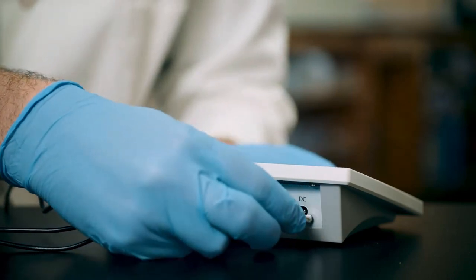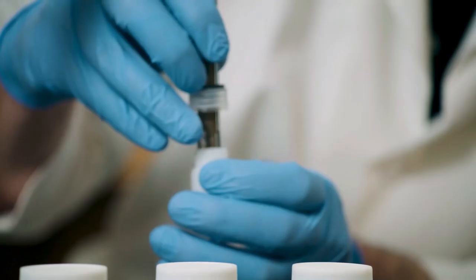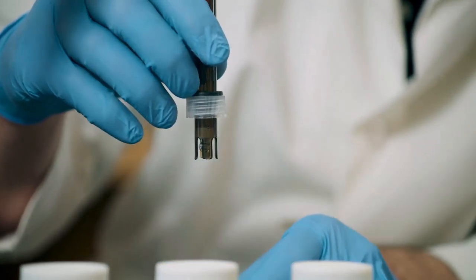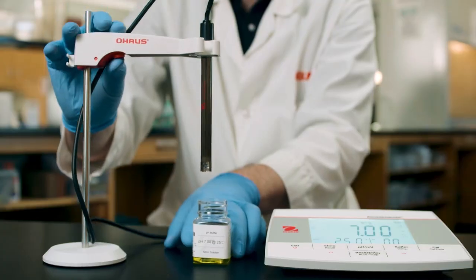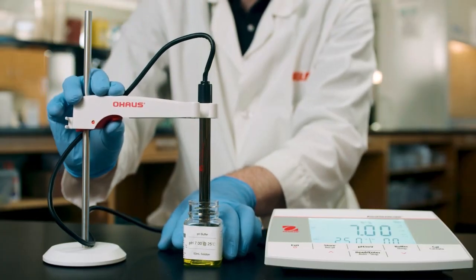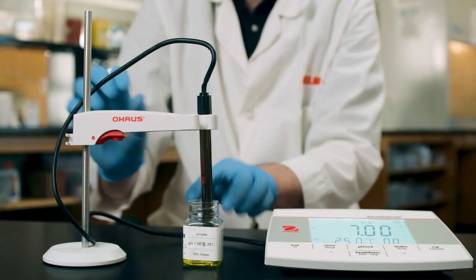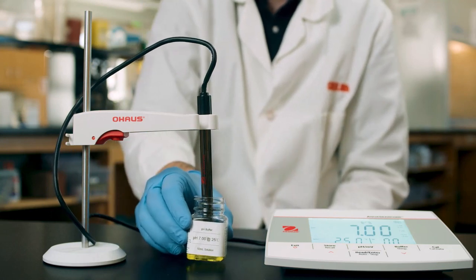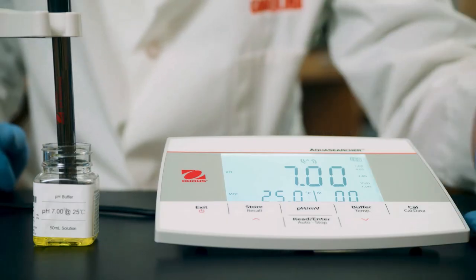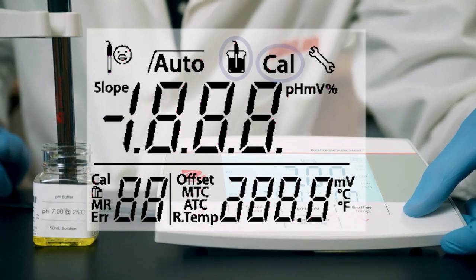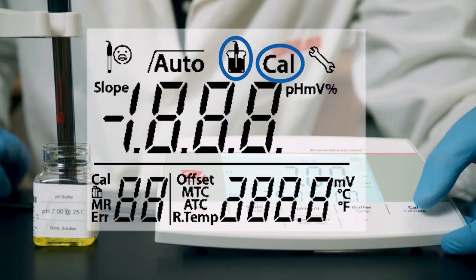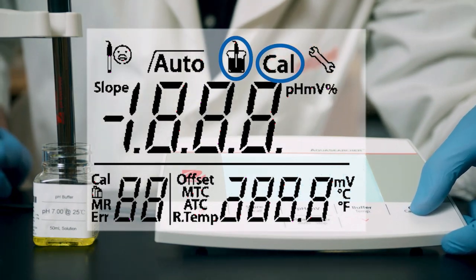First, ensure the meter is plugged in, the electrode is properly attached, and the meter is powered on. Place the pH electrode in the prepared solution. Stir for 4 seconds, and wait an additional 30 to 60 seconds. Press the Cal button. Cal displays on the screen and blinks. A measurement icon will also appear on the top of the screen.